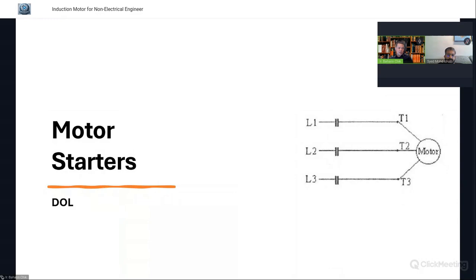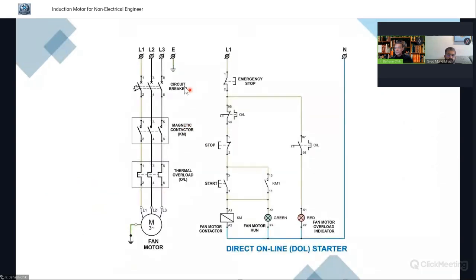We have seen the motor starters just now. DOL, this is a very simple motor starter. So this is the circuit that I wanted to discuss. In terms of control, it is straightforward. We have one line control here. Then when we start the motor, this main contactor KM will get energized. Then in turn, this contactor KM will close the contact, and the power flows into the motors and it runs.